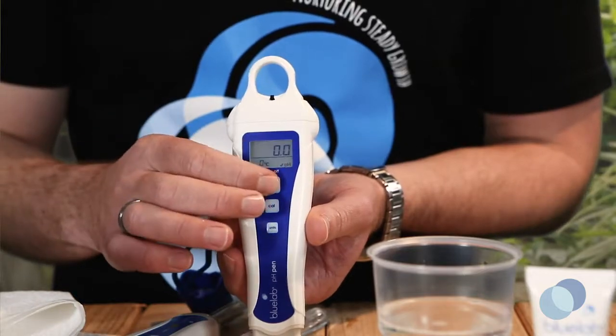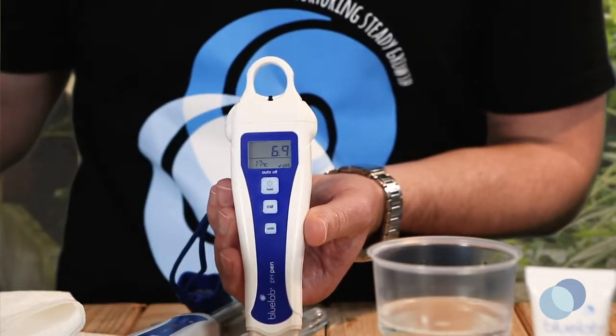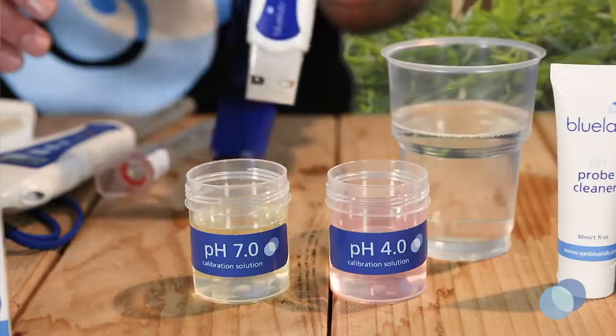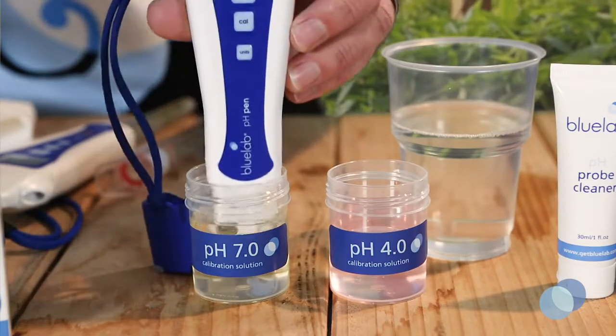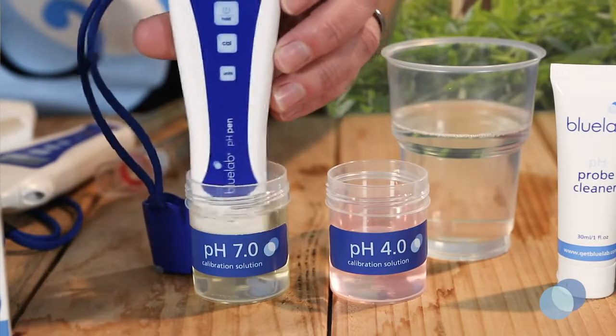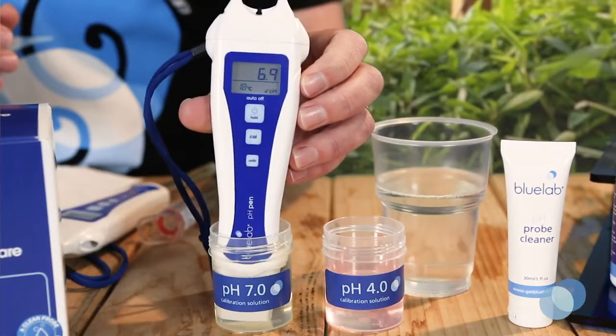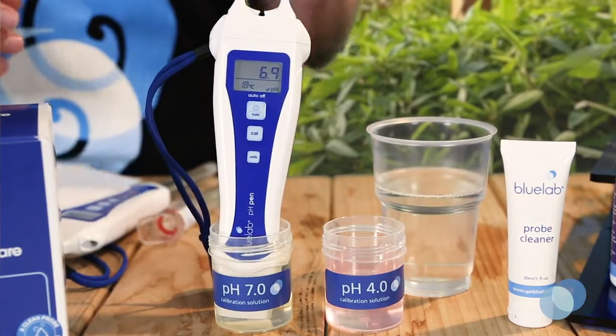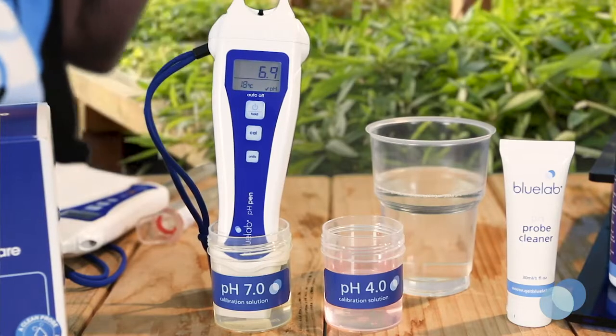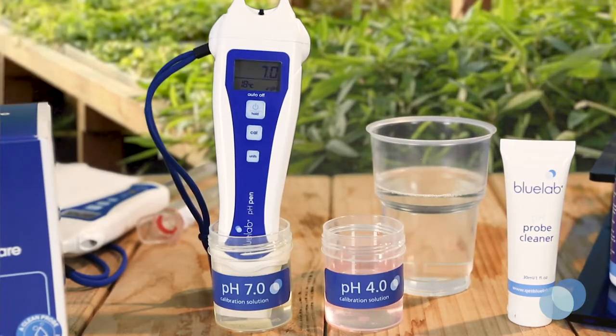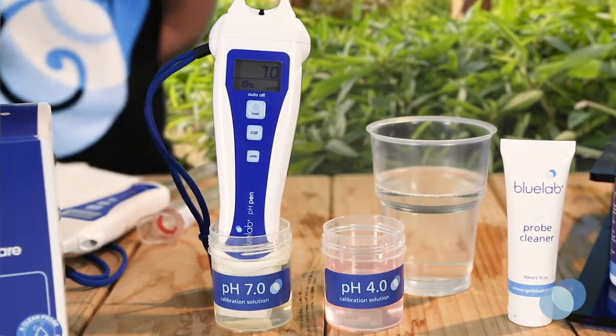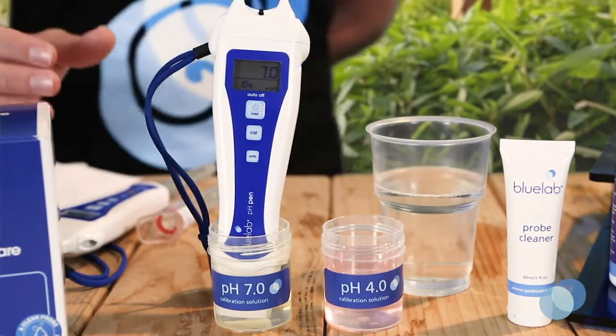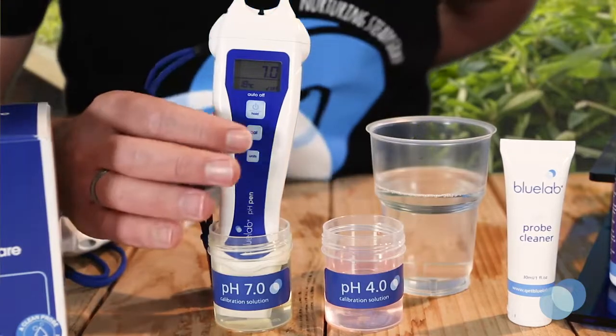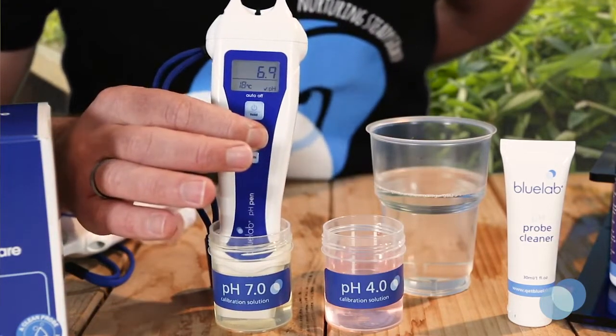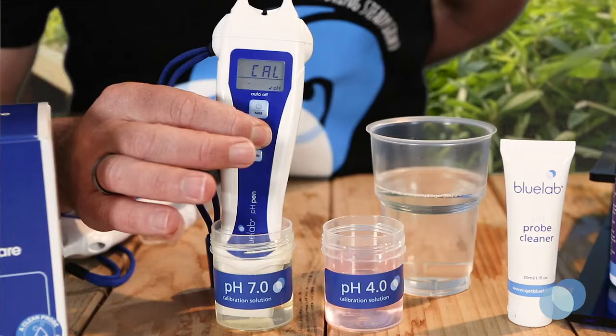Press the power hold button to turn the pen on. Place the probe tip in fresh Bluelab pH 7 calibration solution. Give the probe a gentle swirl to ensure you've got good contact between the probe glass and the calibration solution. Wait until the reading stops moving. Press and hold the cal button until cal is displayed on the screen. Then release the button.